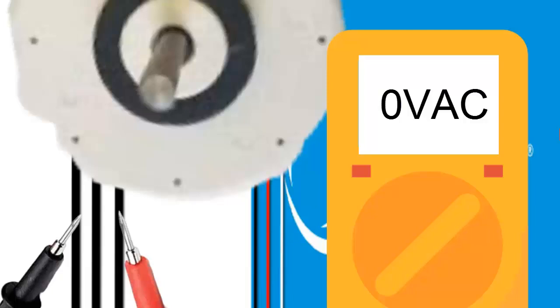12. You can also measure, with the board energized, whether AC voltage is reaching the fan motor through the thick wires when the unit is turned on. If this power voltage is not present, the issue lies in the electronic board, probably in the triac.